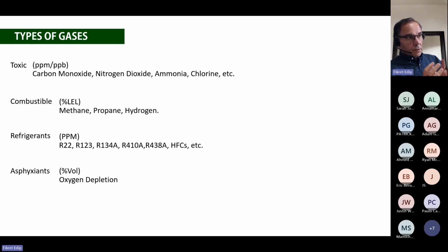A person being asphyxiated, it's immediate. It is not like drowning. With drowning, you have a chance of survival. Being asphyxiated is like a light bulb being switched off. It's gone. For those of you not familiar, the atmosphere has a 21% volume oxygen level in the ambient. The rest is nitrogen. So if the oxygen level descends to 17.9, we are going to give you a low alarm immediately. And below that, it's a high alarm, and you don't want to be there.